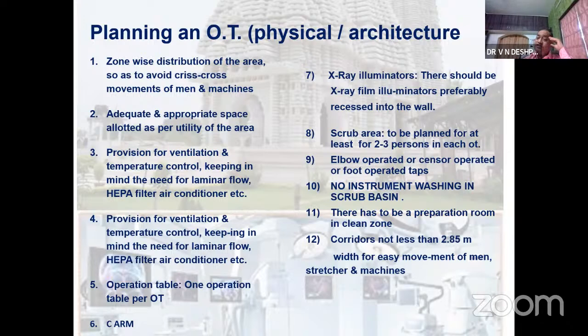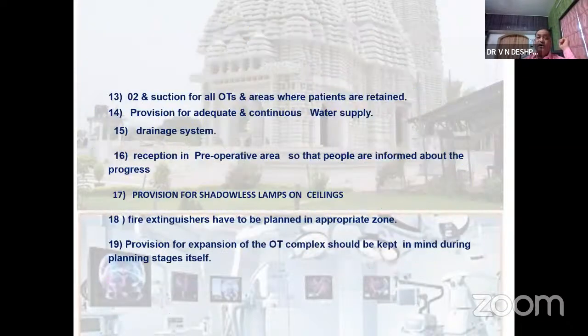No, I suggest no instrument washing in the scrub basin. We have to have a separate space for cleaning up of instruments and evacuating of a suction machine and the materials, which I'll show in later slides, what arrangement I have made in my own hospital. There has to be a preparation zone in the clean zone, corridors of not less than 3 meter width, and for easy movement of men, oxygen suction for all OTs and the places wherever patients are to be held up. Provision for adequate continuous water supply is a must.